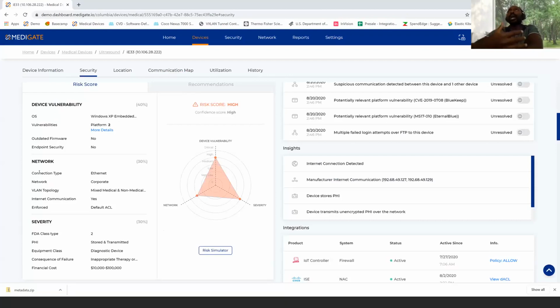If the device sits on a wireless or wired connection versus, say, a gateway connection, like the infusion pump modules I showed you earlier, those would essentially be on a gateway connection that cannot be reached directly via the network. So the security around them is much more than, say, a device that's directly connected to a layer two, layer three network. Additionally, the type of VLAN or layer two adjacency the device has also factors into the reachability or exploitability of those vulnerabilities.